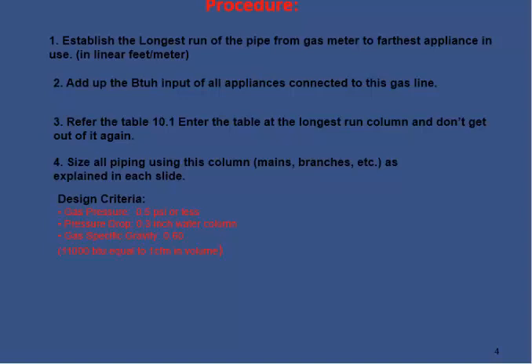Third, refer to table 10.1 as shown here and enter the table at the longest run column and don't get out of it. If we re-read this, we have to establish the total longest distance from meter to the farthest point for calculating the friction losses. Next, we have to size the pipes using the columns as shown in table 10.1.